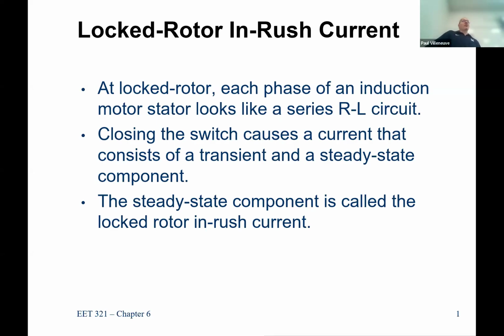So they probably get a lot of use, and it's a lot of starting and stopping, which, as we saw in lab this week, you can hear the motor straining a little bit because of those locked rotor conditions. And then over time, it gets better. So motors that are operated for continuous duty have a little less beef to them, if you will, than ones that are starting and stopping all the time. Like compressor motors, when they start and stop, especially if it's cycled on and off a lot, that's particularly hard for the motor. Most compressors, right, aren't just a standard compressor where it just compresses air.